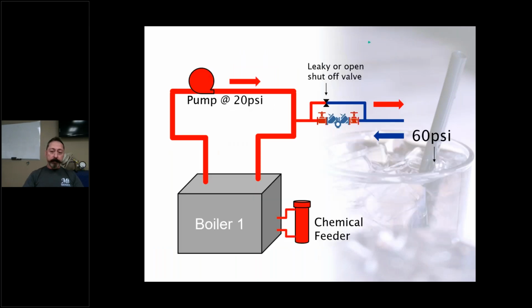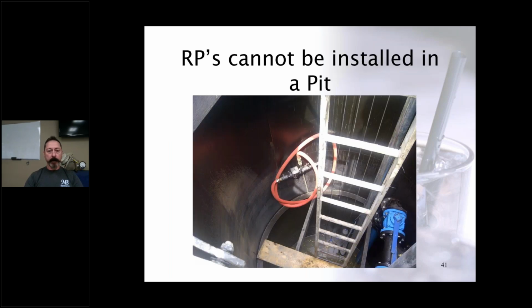Again, even if you have a backflow preventer and it's being tested every year and everything's functioning perfectly, you can still have that event if your incoming supply pressure drops and the pump on that boiler, due to thermal expansion, is greater. It will back pressure that contaminant, the glycol or whatever system or heat medium they're using in there, into the potable water supply. So it's a false sense of security if you think there's a backflow preventer there and it's not functioning properly.